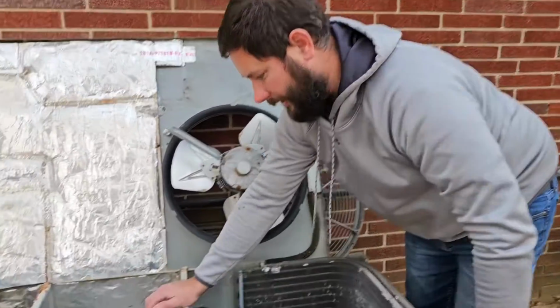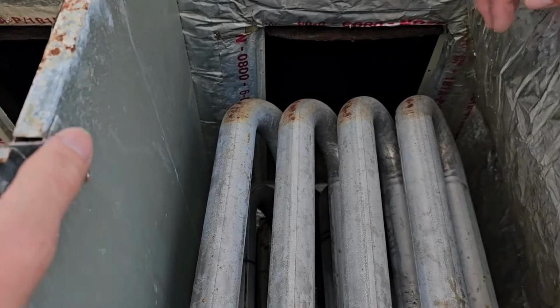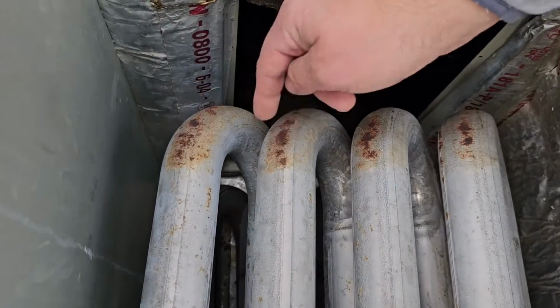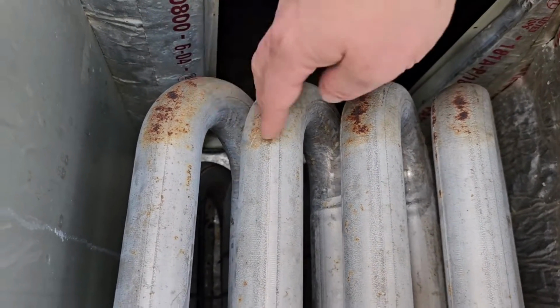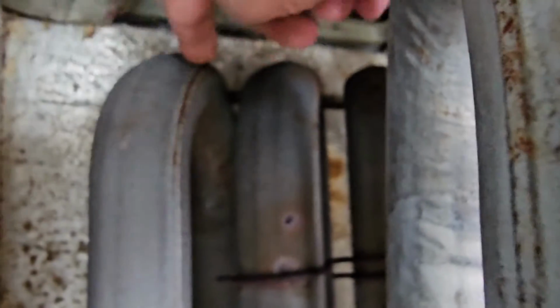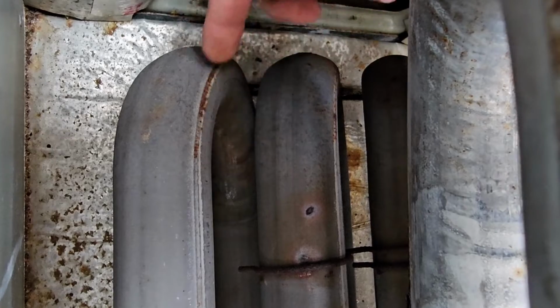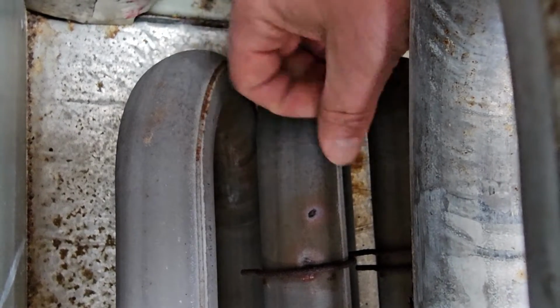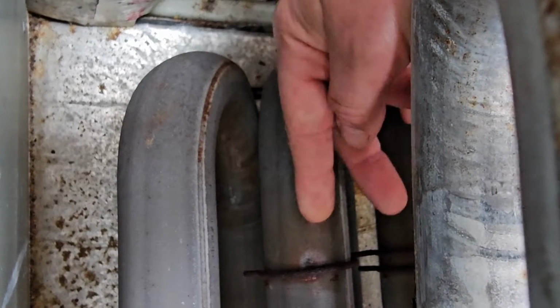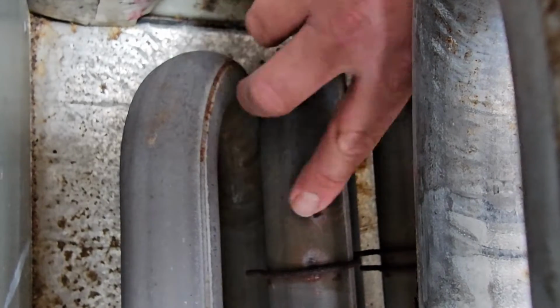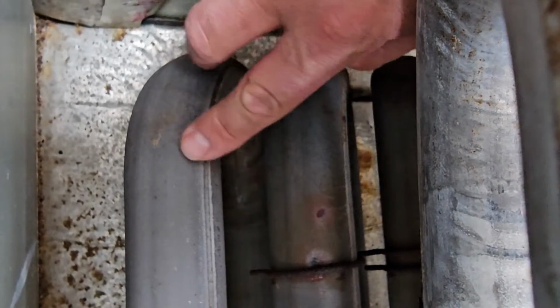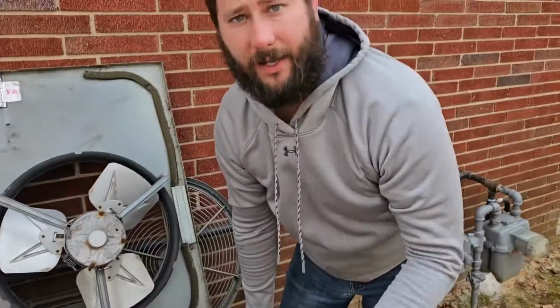On the heat exchanger, there's a bunch of rust, but there's no holes. See, bunch of rust. I always look beneath the first set and I look at this line, okay? You see that line? I'm always looking at that and trying to find out if there's a hole. And there are no holes. So I'm going to let the customer know that there are no holes in the heat exchanger. It is very rusted, but it's going to get you by.